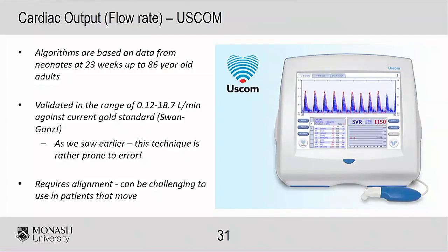And it's validated in the range of 0.12 to 18.7 litres per minute against the current gold standard, which is the Swan-Ganz catheter. But as we saw earlier, this technique is fairly prone to error, so might not be the best validation that you can use in the world. Well, it still probably is the best validation you can use in the world because there's not many other options.